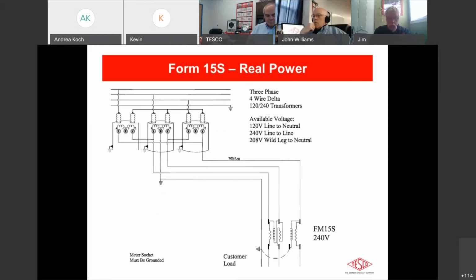The next one is, as I mentioned before, the 4-wire delta application with the self-contained. This is the 15S meter, same situation as its transformer rated counterpart, the 8S. So again, you have the 4-wire delta with the center tap ground on one of the legs. And you have the wiring, as you see here, directly in for the 3 lines, one side being the wild leg, and that is the one that's attached to the ground point. And the other 2 legs are tied across the single voltage element here.